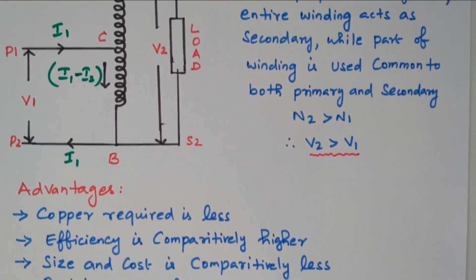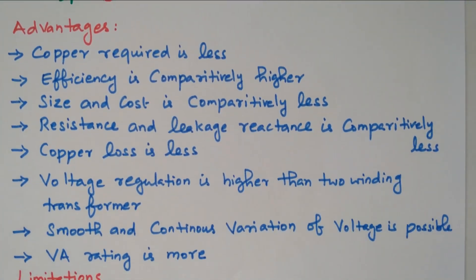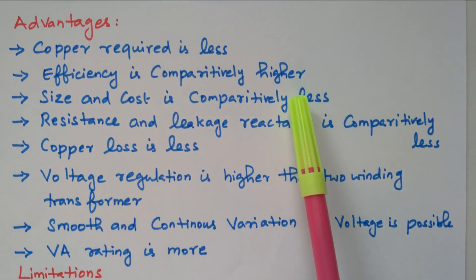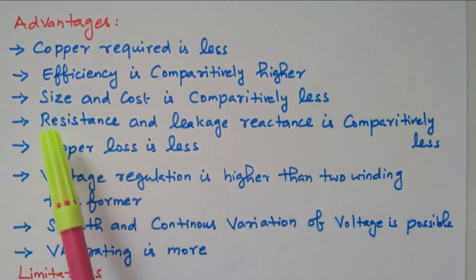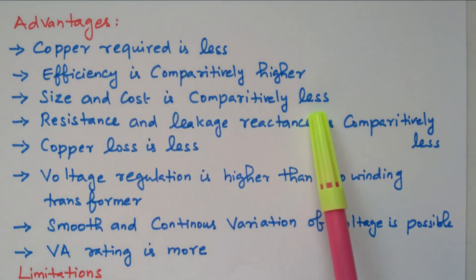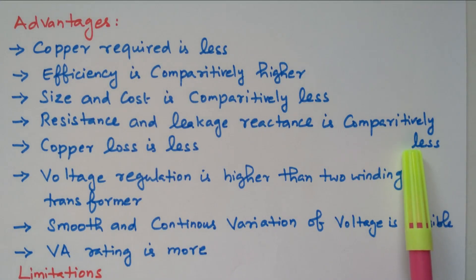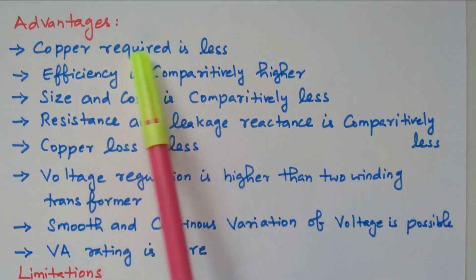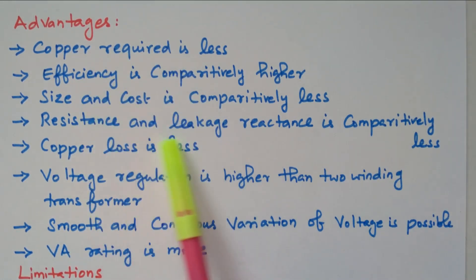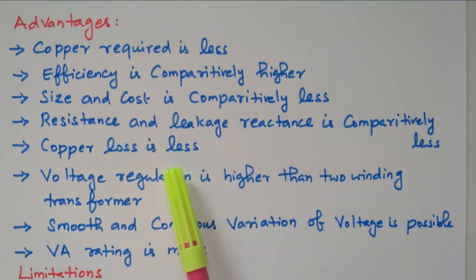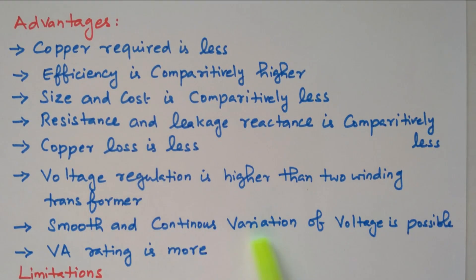Now for the advantages: copper requirement is less because only one winding is available. Efficiency is comparatively higher with no drop. Size and cost are comparatively less. Resistance and leakage reactance are comparatively less. Copper loss is also lower. Voltage regulation is better than the two-winding transformer. Smooth and continuous variation of voltage is possible. VA rating is higher. These are all the advantages.